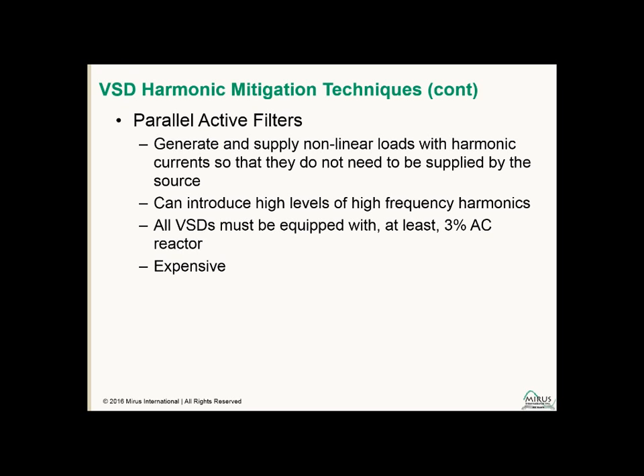These can also introduce high frequency harmonics as they also have IGBTs in their operation. So you're going to have similar issues that you'd have with an active front-end drive. And if you want to make an active filter effective, you're going to need to have at least a 3% AC line reactor on all the variable speed drives connected to that system.